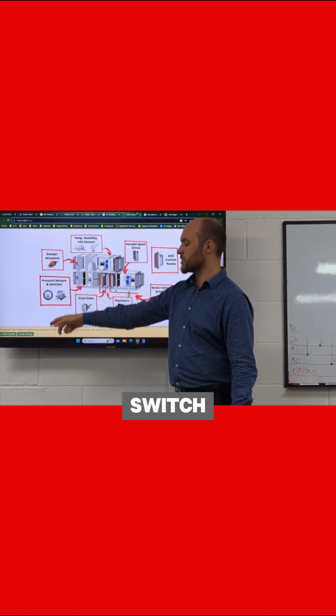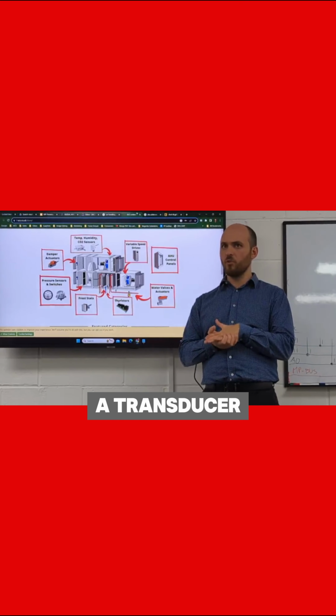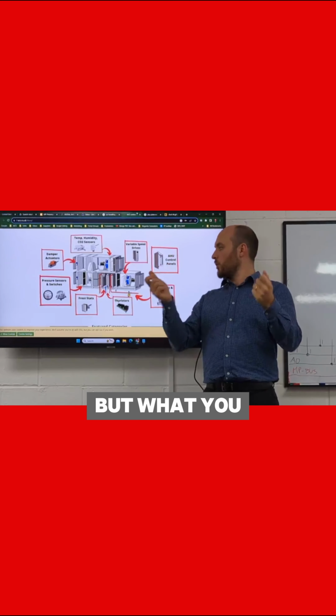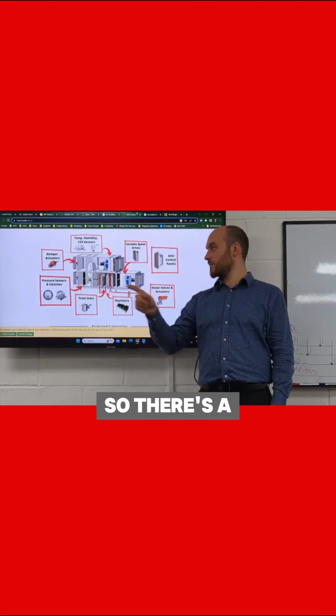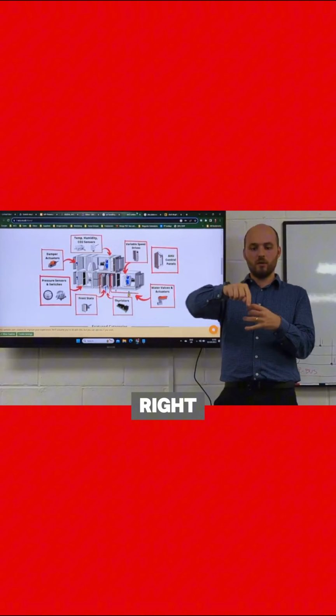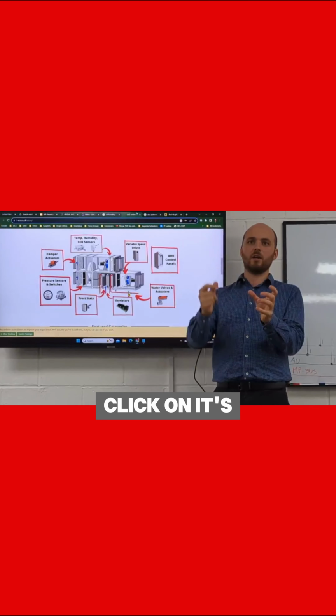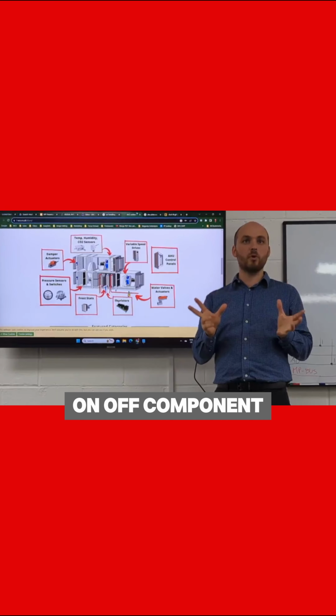That's a pressure switch. It's a lot cheaper and simpler than a transducer, but it's the same idea - it's measuring the airstream. What you do is set a threshold on it. There's a little switch and you'd say, right, 200 pascals. When I get there, click on. So it's like an on-off component, you'd call it a switch.